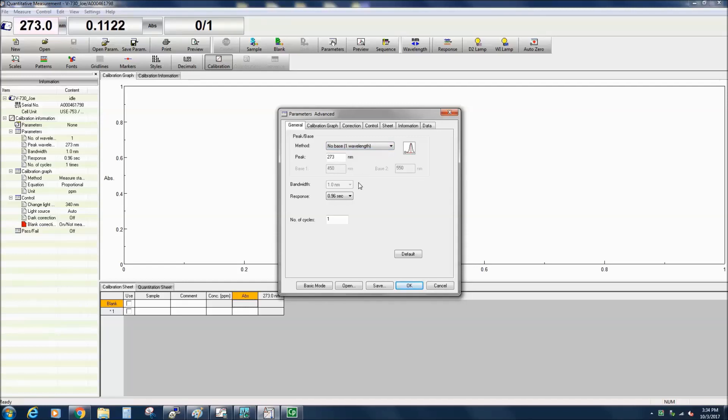The bandwidth determines how much light reaches the sample. The smaller the bandwidth, the less light throughput and the lower the signal to noise, but you can achieve better peak resolution. If you are using a V730, the bandwidth remains fixed at one nanometer.